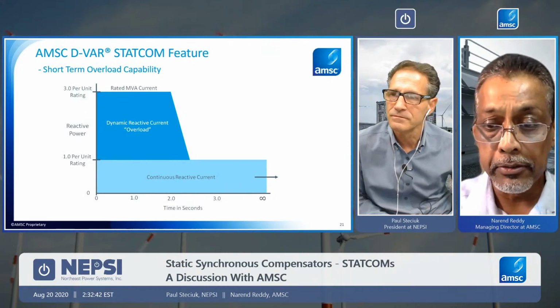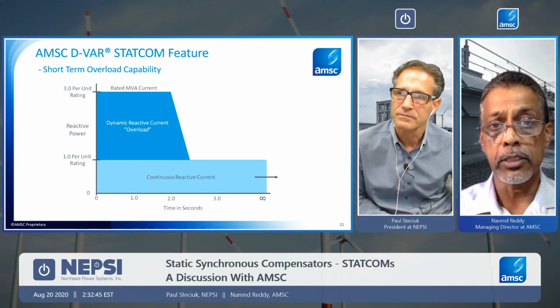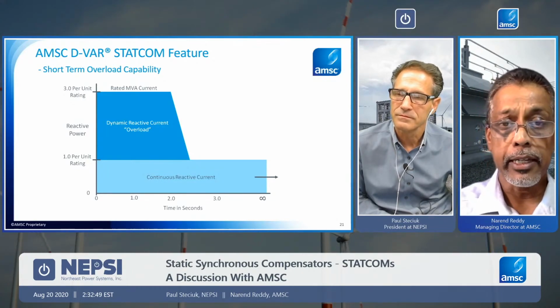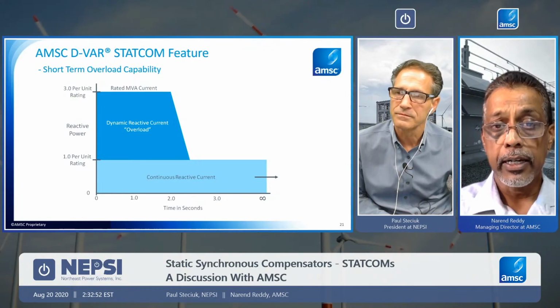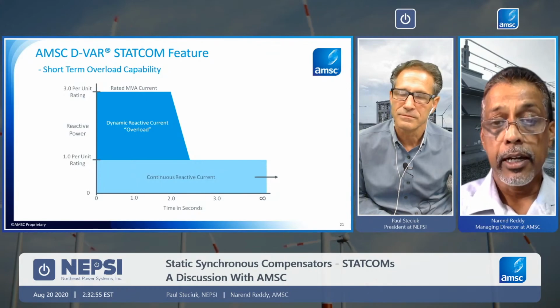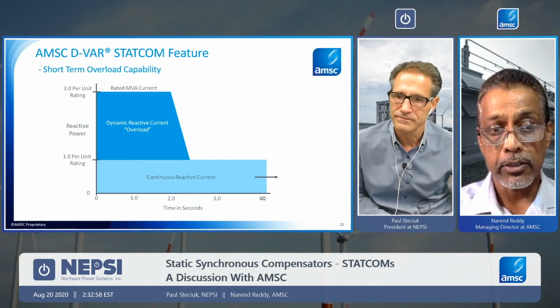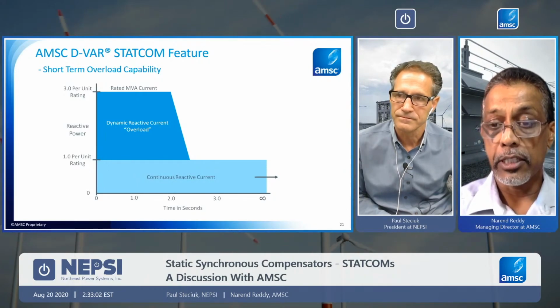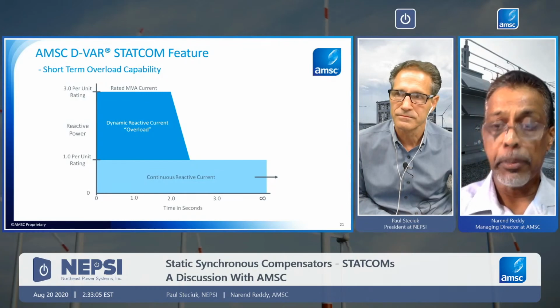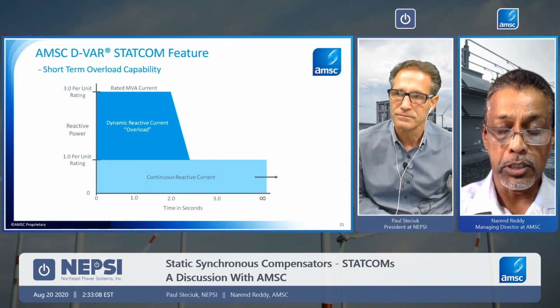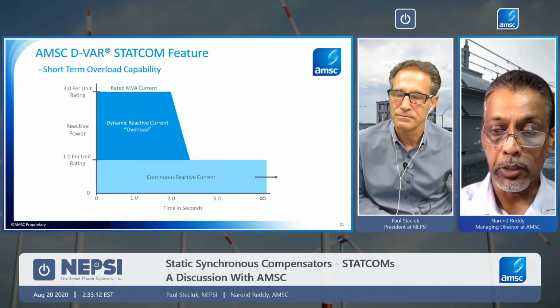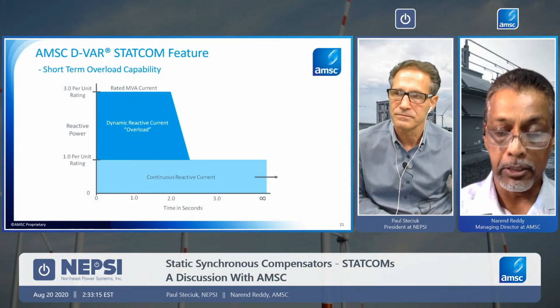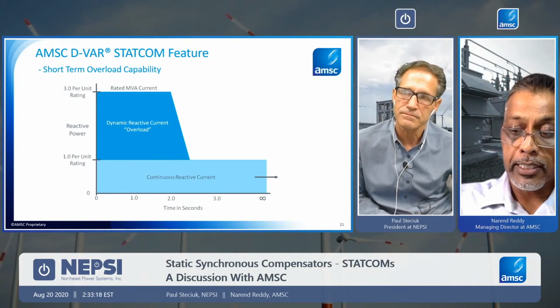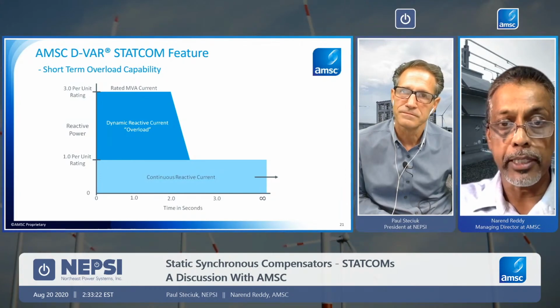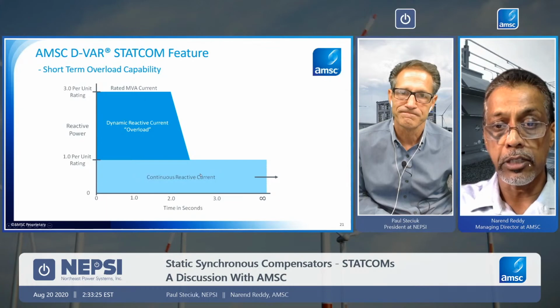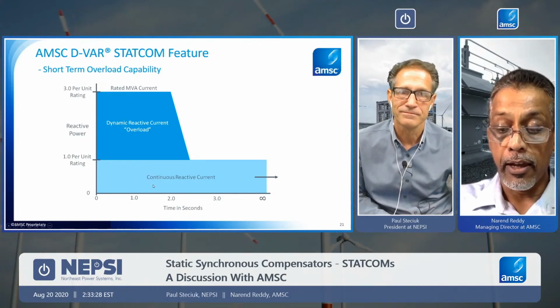Another point that I'd like to point out here, I mentioned short-term overload, which is basically a time-based capability for the DVAR. For 2 seconds, the DVAR can put out 3 times its rated current. What that means is that when you have faults or deep sags, a 4 megavar device can essentially put out up to 12 megavars. The impact of that 12 megavars is that you're going to have a voltage rebuild, or you're going to bring some surges down, depending on how much current you're putting in. So this is something that's really reserved for transient applications. We don't use that for normal regulation.